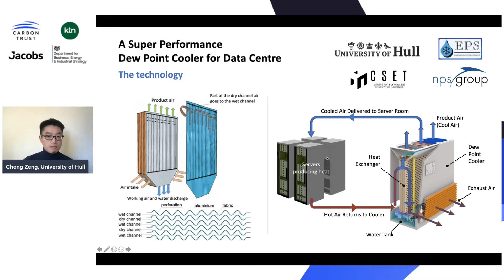On the right we made a simplified animation. Servers on the left produce heat, and we want that heat absorbed by our cooler. The hot air returns to the cooler and cools down inside the heat exchanger while the water evaporates. Part of the humidified warm air exhausts into the ambient, and part of the cooled product air is supplied back into the room. That's how the technology works.